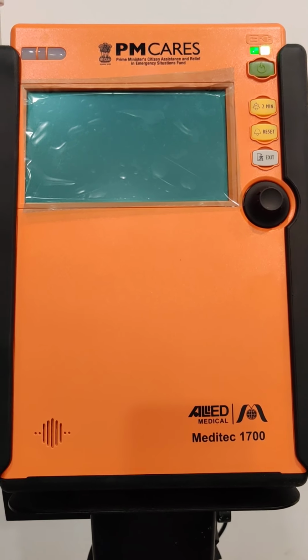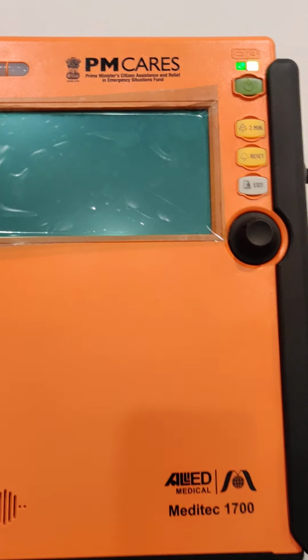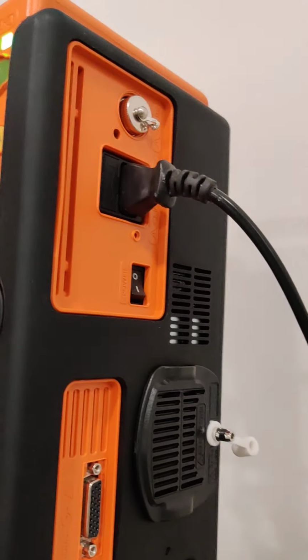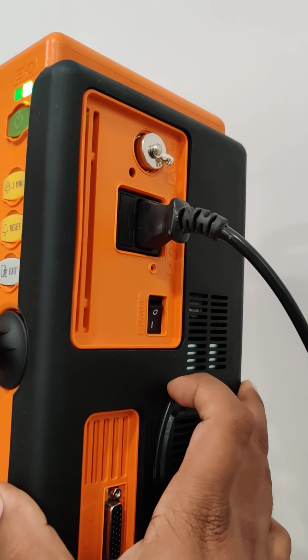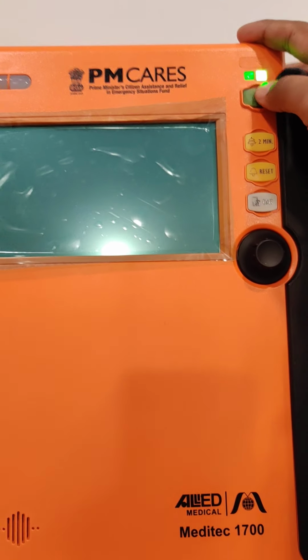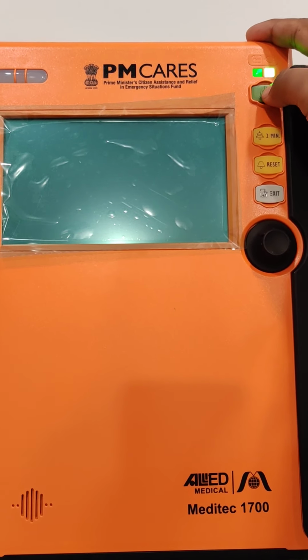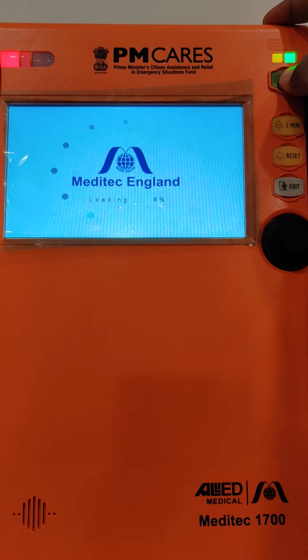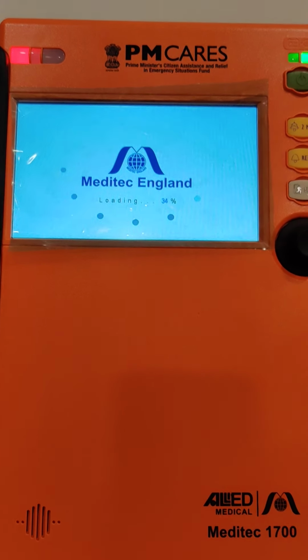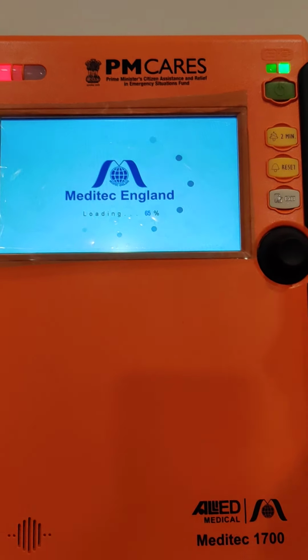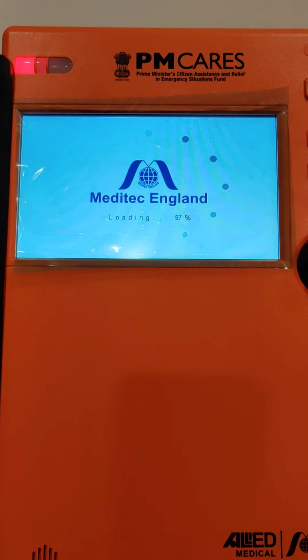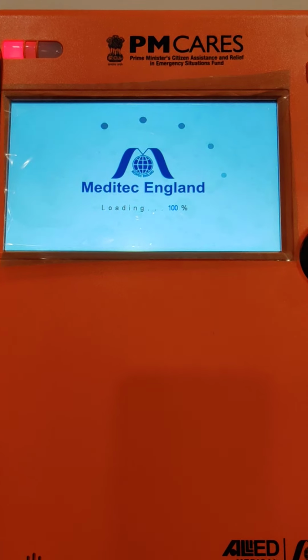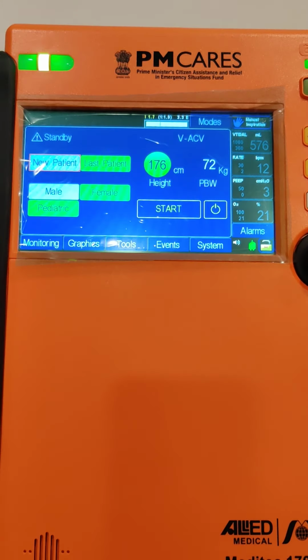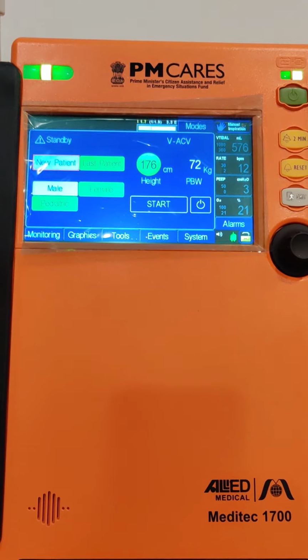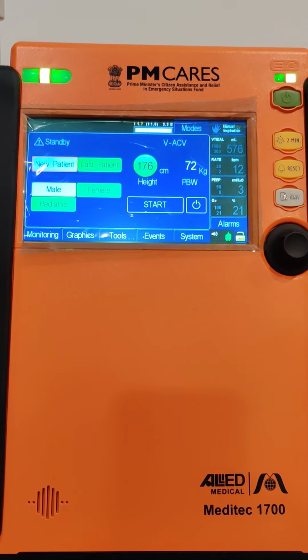Now coming to turning on and turning off this ventilator. For turning on, first there is an on-off switch on the right hand side. This has to be moved to position 1. You will get a long beep sound, and you have to press and hold this on-off button on the front, that is a green color button. As soon as the beep sound goes off, you remove your finger, and you will get a Meditec England logo on the front. This is the user interface or the standby screen that you will get after turning on the ventilator.